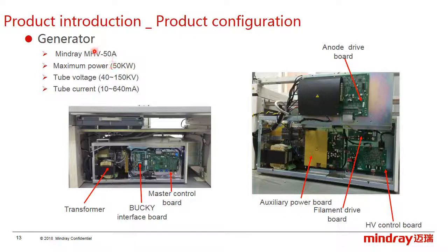For the generator, the model is MHV-50A. This generator is placed under the patient table. In the front of the generator, you can see the transformer, the BUCKY interface board, and the master control board. Turn over the master control board, and you can see the anode drive board, the auxiliary power board, and the filament drive board.